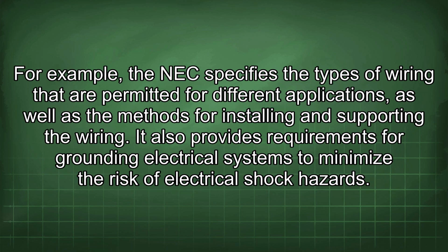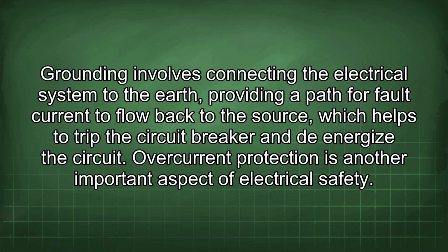For example, the NEC specifies the types of wiring that are permitted for different applications, as well as the methods for installing and supporting the wiring. It also provides requirements for grounding electrical systems to minimize the risk of electrical shock hazards. Grounding involves connecting the electrical system to the earth, providing a path for fault current to flow back to the source, which helps to trip the circuit breaker and de-energize the circuit.